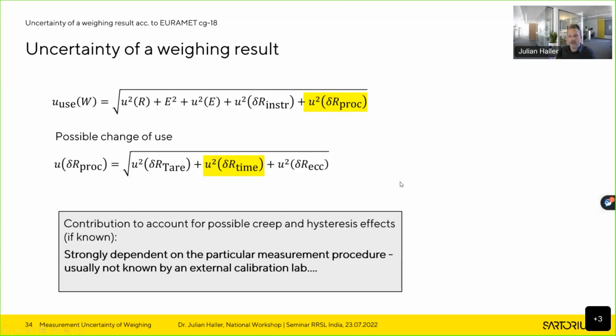And then just to add, what is also mentioned in the question, a big drawback of legal metrology for weighing instruments is the fact that the smallest possible e value is 1 milligram. And we nowadays have ultra micro balances. So e is, let me calculate, 10,000 weighing steps. And this is really a problem of legal metrology, that no e and no MPE smaller than a milligram or half a milligram is possible, which means that for an ultra micro balance, the legal metrology requirement, the MPE, is really ridiculous, because it's 5,000 digits.